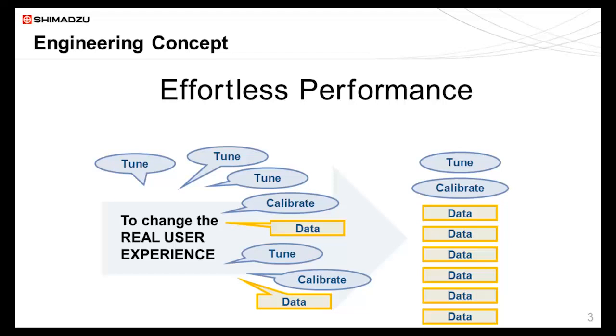The engineering concept of this Q-TOF instrumentation is effortless performance. Conventionally, Q-TOF has been a very naive instrument to utilize in routine. You have to tune and calibrate every so often to get the proper data, and even if you've got the data, you've got to calibrate again to ensure that you've got usable data. Our intention was to change this user experience to something more organized and more productive, such that you tune once and you calibrate once and you keep on generating usable data.